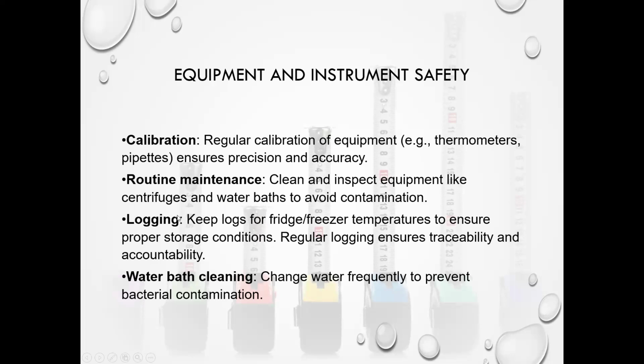With CLIA standards, we should be keeping logs for all of our calibrations and maintenance. And by standard, those logs need to be kept for 2 years. If we are using water or water baths for any reason in our laboratory, we should be making sure we're cleaning those out, and any water that is used for diagnostic testing needs to be tested for bacterial contamination at least monthly.